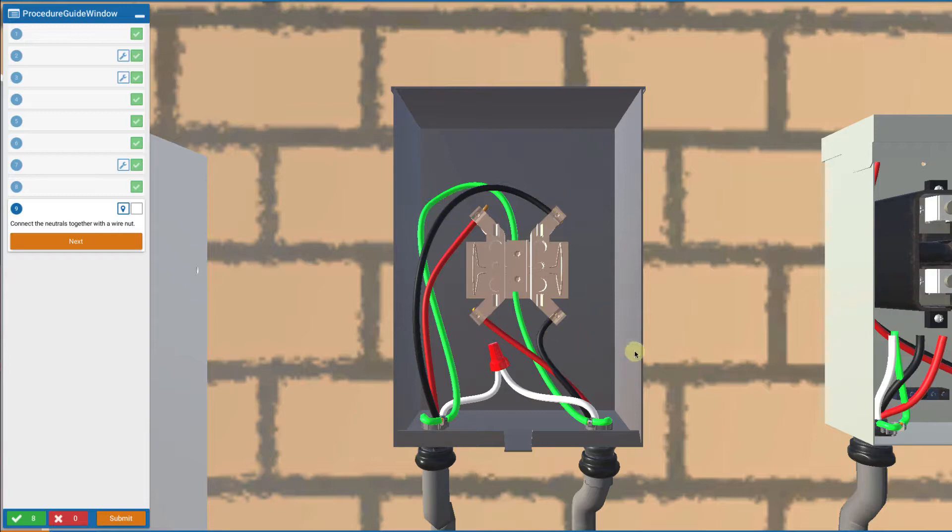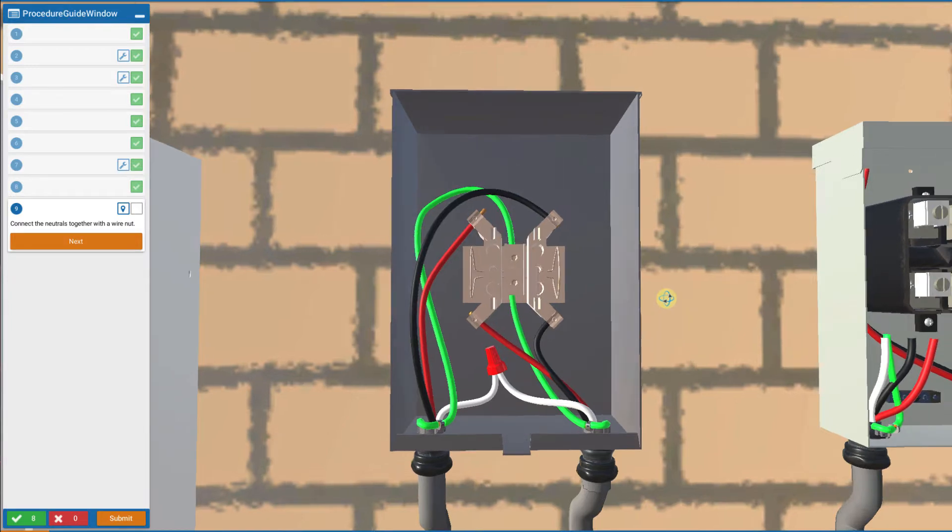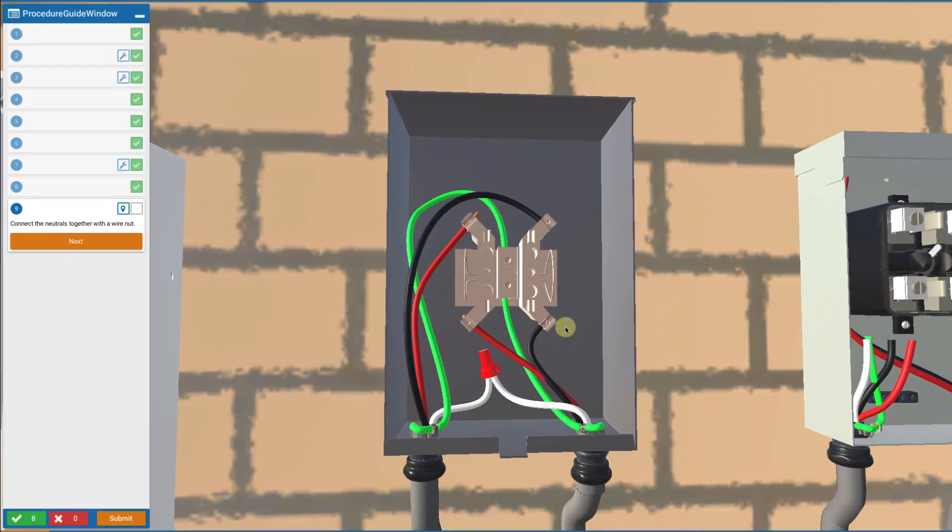So now we have black and red coming in on the top, black and red coming out on the bottom, grounded equipment grounding conductor connected to the box, and neutral passing through. Now we finish by grounding the wires to the grounding bushings.